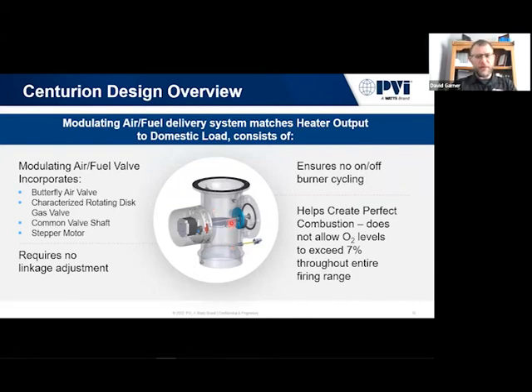With this air fuel valve right here on the air side, there's the shutter that's going to open and close, and on the same shaft, there's a little plate here, and that's a custom cut orifice. As that valve opens, it's going to allow in the appropriate amount of gas to maintain that 10-to-1 air fuel ratio that ramps up and ramps down.